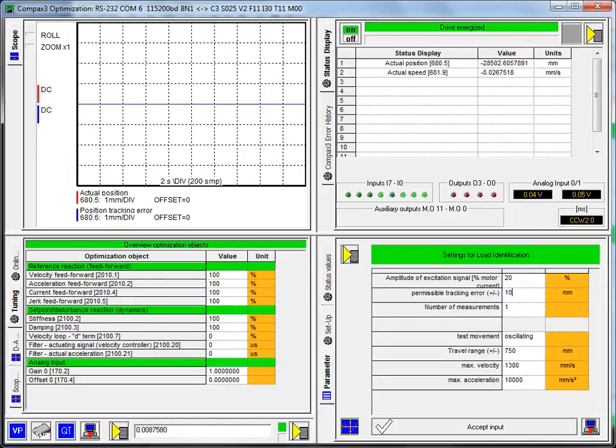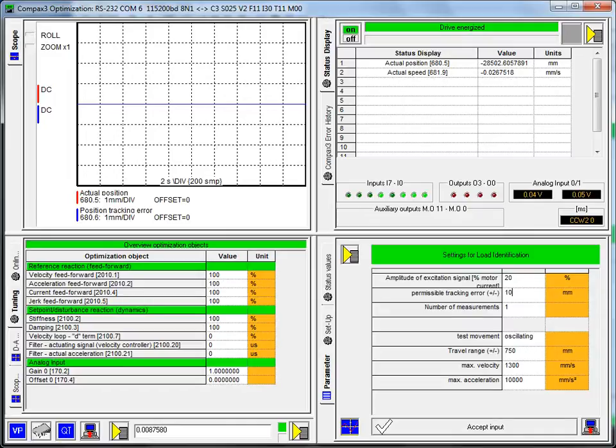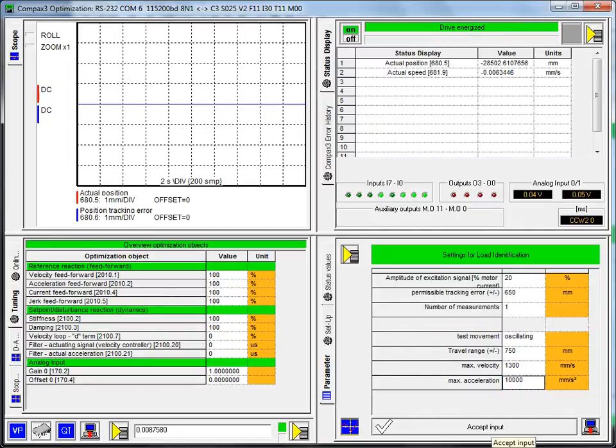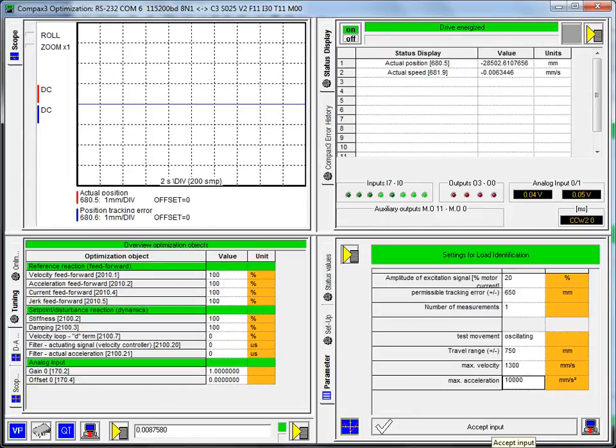The default value is 10 and that presumes that the motor is one millimeter per rev. So if you're using in degrees, 10 would be a fraction of a revolution. So you would want to increase that to 3600 to be roughly 10 revolutions of the motor. We recommend doing the number of measurements at least twice, if not three times, to ensure that the algorithm is consistent in the inertial value that it's calculating. I'm just going to do this once as a demonstration. For most belt drive actuators, 7500 would be a good maximum acceleration value. For most screw drives, those are 1 to 2g maximums. So the default value is 10000 millimeters per second squared, which is roughly 1g. I'm going to go ahead and leave that. Go ahead and click accept input.